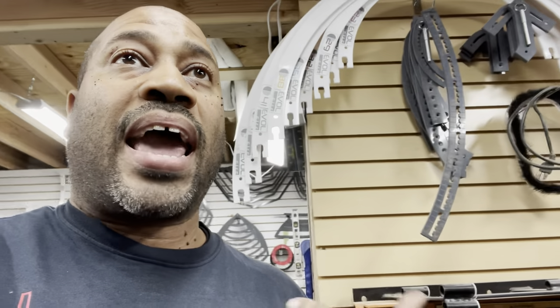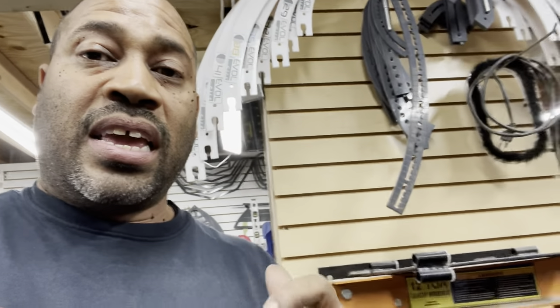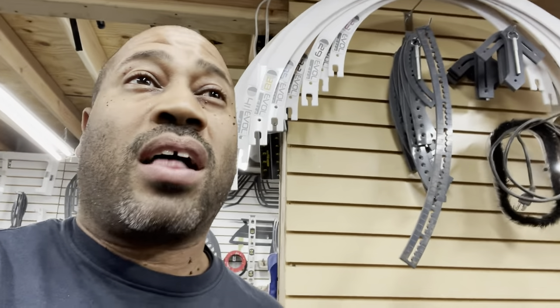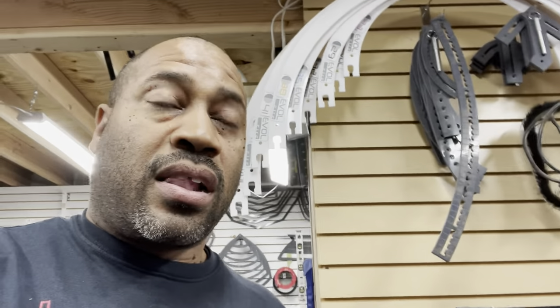A lot of people asked me to make this video and put up some part numbers so DIY guys know what to use. The main difference between crimpers is the metal they're made of. A cheap crimper will flex and won't exert enough force to properly crimp the connector. Get a good name-brand crimper — you can get one for around $30 at Home Depot. They carry Klein, which is the industry standard, and Klein makes a good crimper.